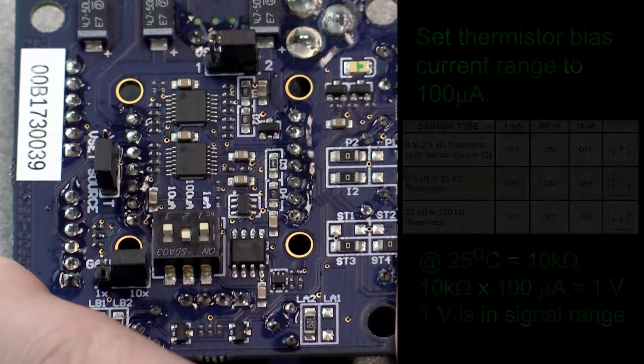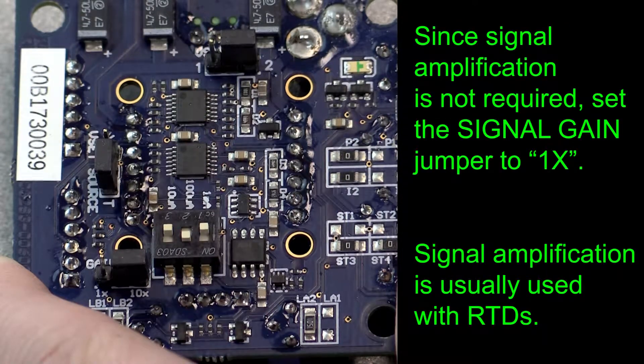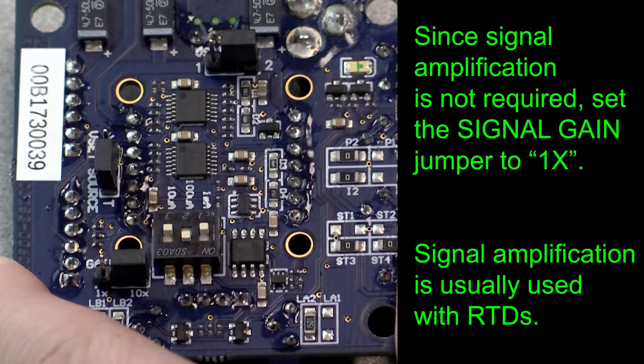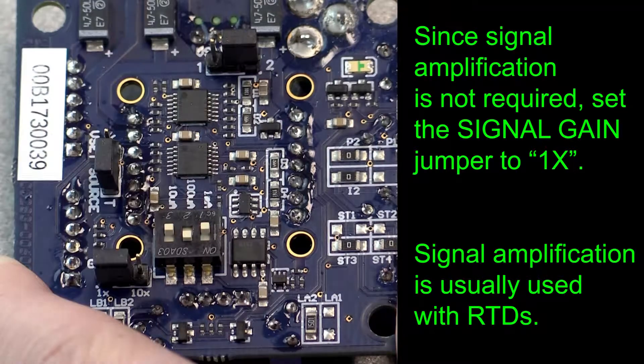The signal gain jumper allows us to amplify sensor voltage. Since the sensor voltage is in the acceptable range, we use the 1x position and the sensor signal will pass through without amplification.